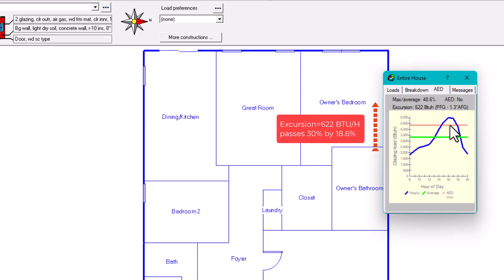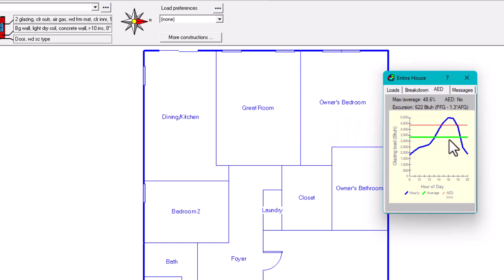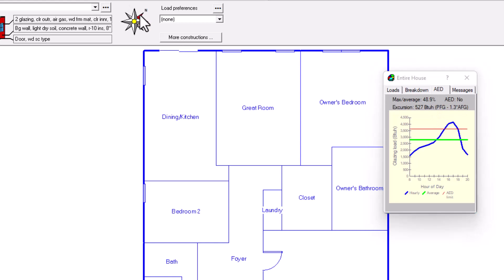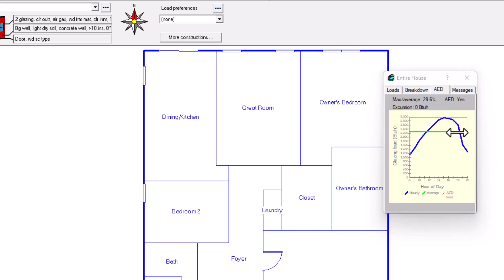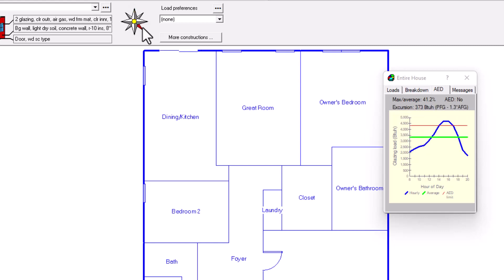The excursion formula makes sense: PFG minus (1.3 × AFG). You are subtracting from the peak down to the AED Limit — which is the AFG plus 30%. We'll go back to normal orientation now, where AED says Yes and no zoning is needed. For a basement plus first floor plus second floor configuration, zoning would be strongly encouraged.